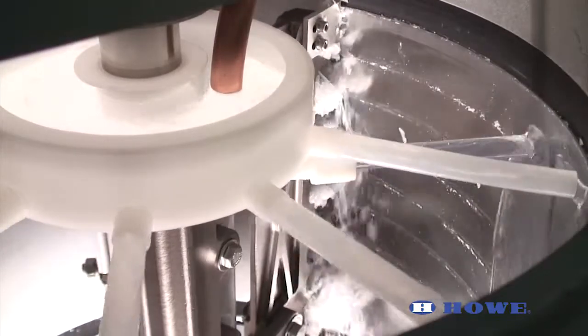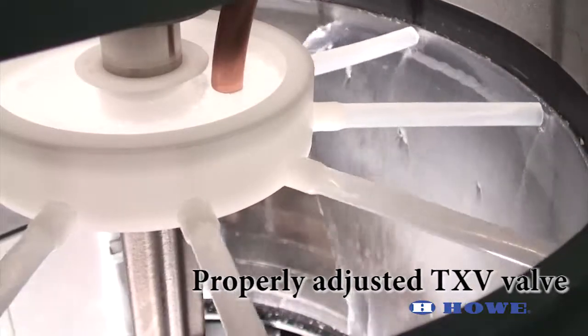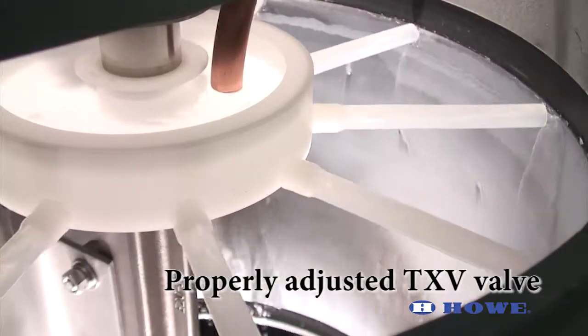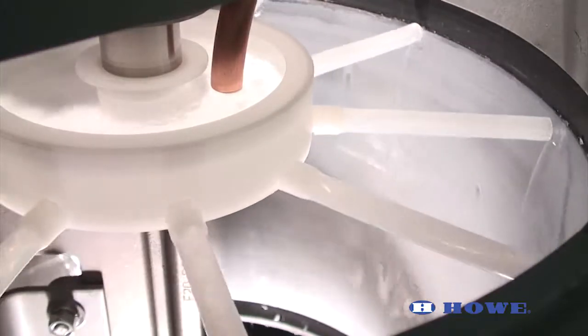When ice is freezing and harvesting over the entire evaporator from the top all the way to the bottom on each rotation, the unit is properly adjusted.